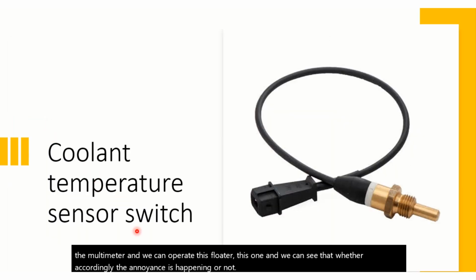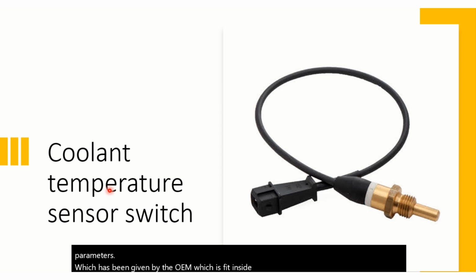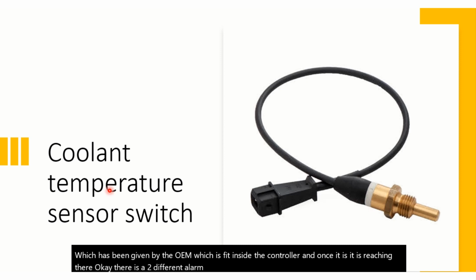Now, coolant temperature sensors. In the earlier slide we saw how to check the quantity of the coolant and how we generate the alarm if it goes below low level. Similarly, if the temperature increases for whatever reason, we have to continuously monitor the coolant temperature, and if it goes beyond the specified value like 100 degrees, it should immediately shut down the engine. There is a set of parameters given by the OEM, fitted inside the controller, and once it is reached there are two different alarms, one analog and the other digital. With both alarms, it takes an action and shuts down the engine.